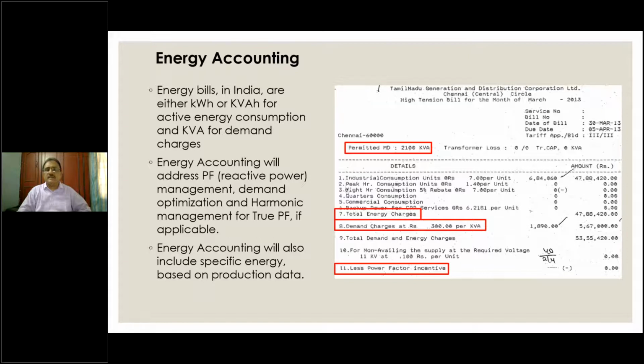Normally, I do not mention the name of the customer, but here, since it is public sector and nobody will actually find fault with me, this was done in 2013, as you can see here. The permitted demand for this facility was 2,100 kVA at that time. Right? They have not reached this 2,100. They have reached less than 90%, but minimum payable is 90%. So 2,100 multiplied by 0.9 will give rise to 1890 kVA. So they are paying for 1890 at the rate of 300 at that time. Now it is 350 in Tamil Nadu. So 1890 multiplied by 300, they are paying 5,67,000 rupees fixed in the power bill towards the maximum demand, towards the contract demand. Now let's go to the next slide and come back again.